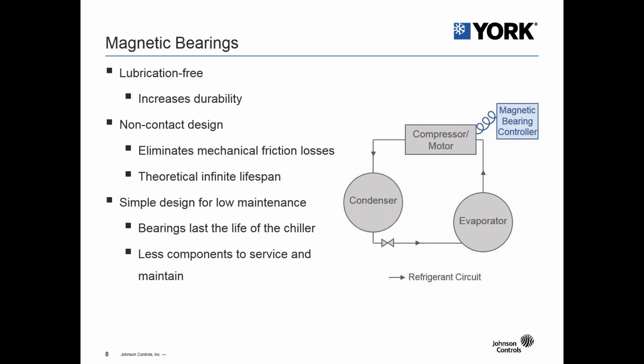So moving on to magnetic bearings. Magnetic bearings, like the refrigerant lubricated bearings, are oil-free. However, the magnetic bearings are the only lubrication-free bearing technology. So this increases durability. There's no metal-to-metal contact, so there's no mechanical friction losses, which increases the efficiency of the package. And there's also a theoretical infinite lifespan because there's no wear and tear on the bearings themselves.